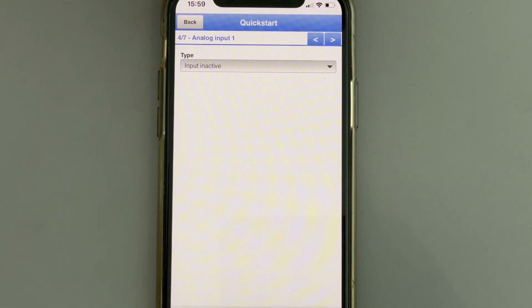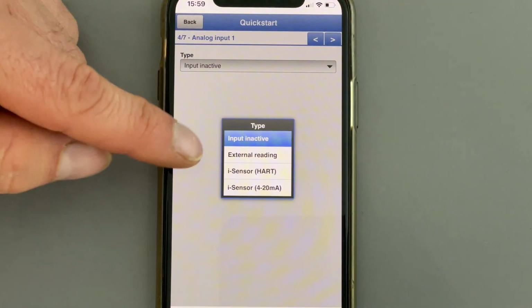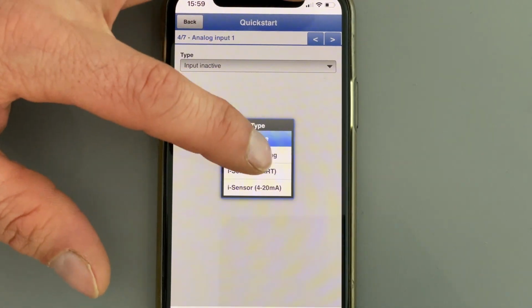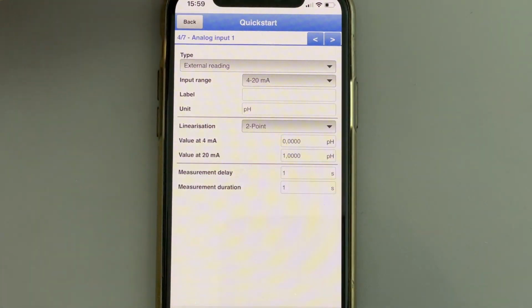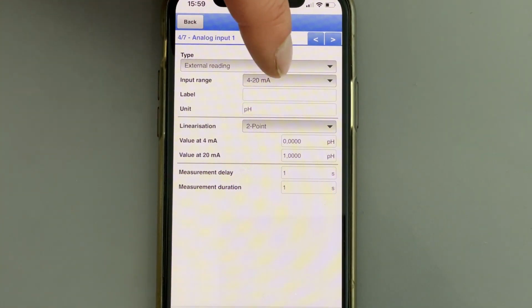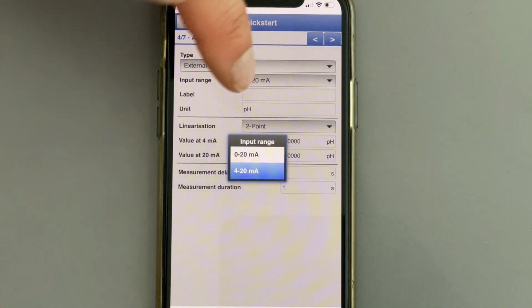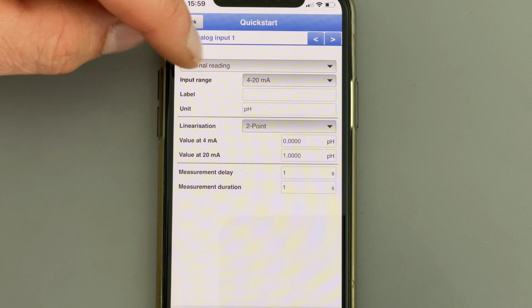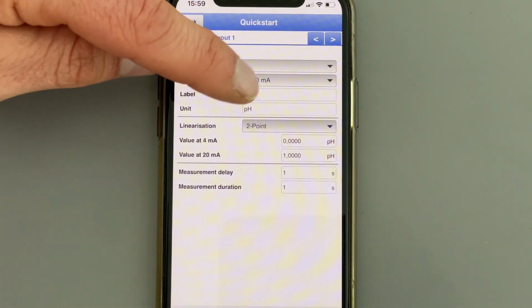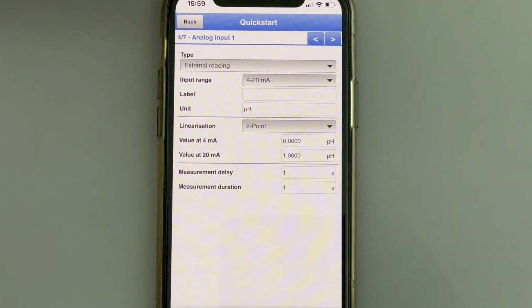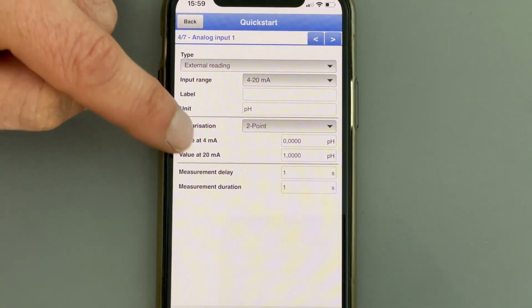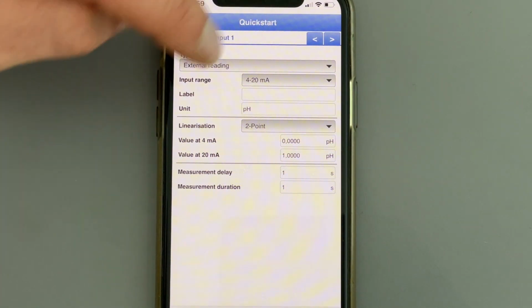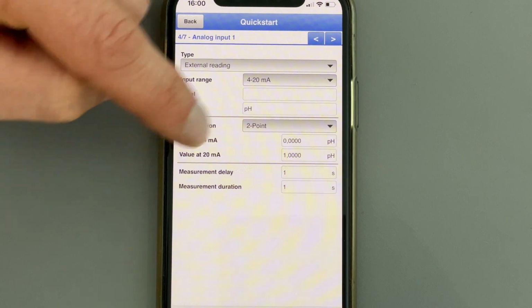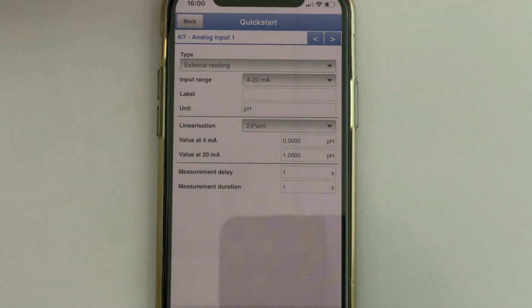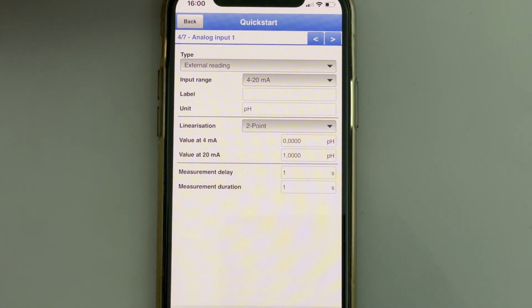On the next page you have the option for activating different analog inputs and outputs. And here you can choose an external reading or an i-Sensor, which is our own. On the external sensor you can use any standard 4 to 20 milliampere sensor, for example, or 0 to 20 milliampere, and you can choose the units and a label. And also here a 2-point calibration. That means at 4 milliamperes it has 0 pH, for example, and at 20 milliamperes it has a pH of 14 if it's a pH sonde, for the whole range between 0 and 14.